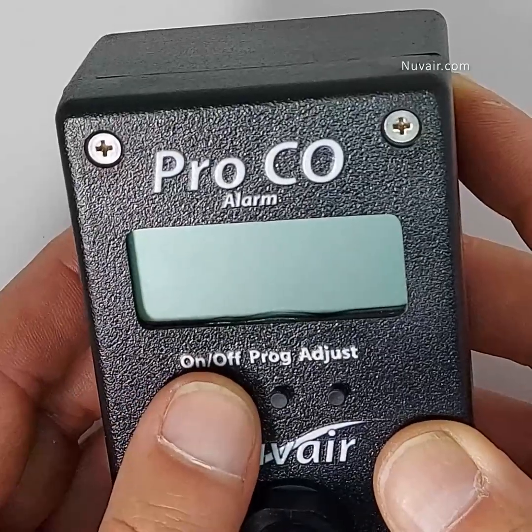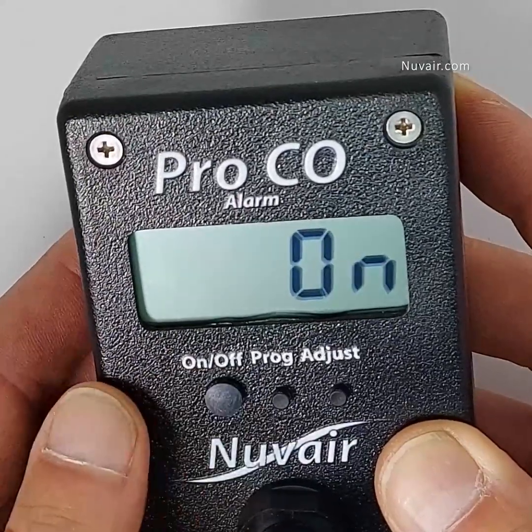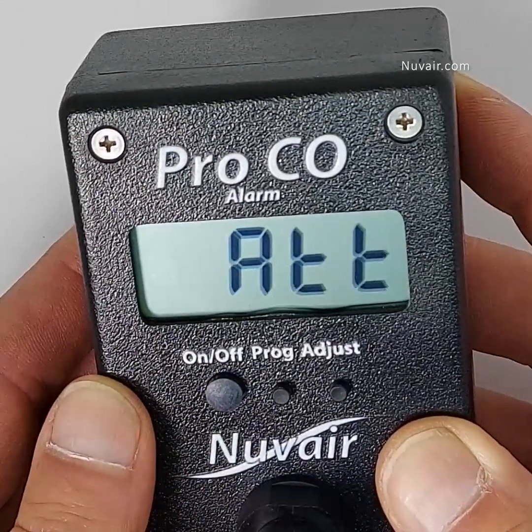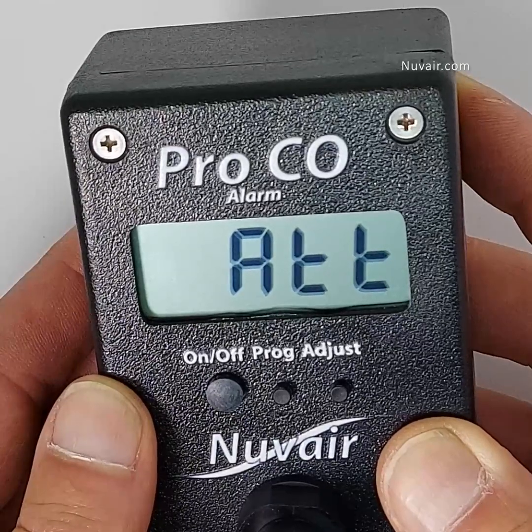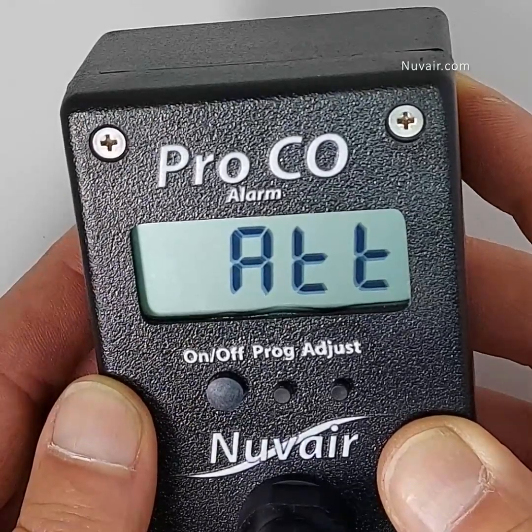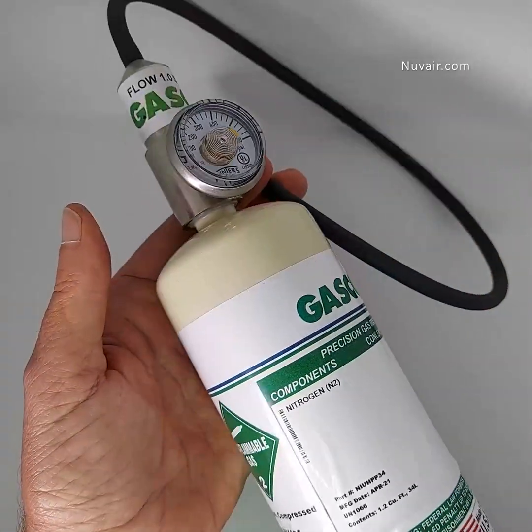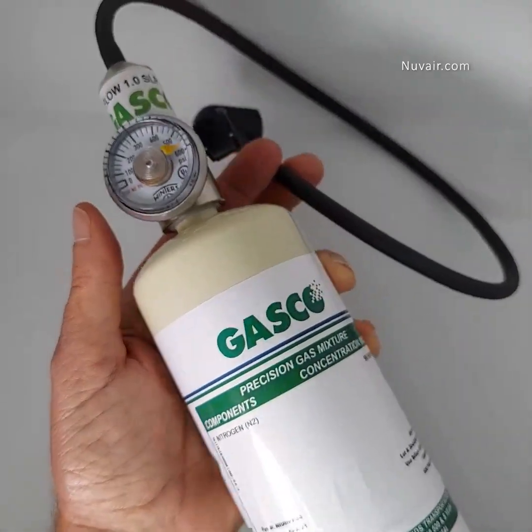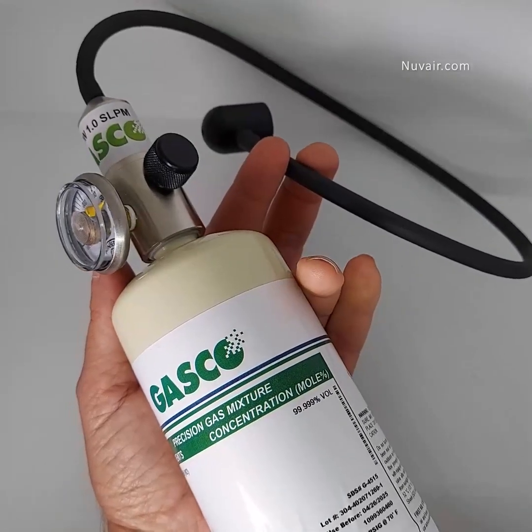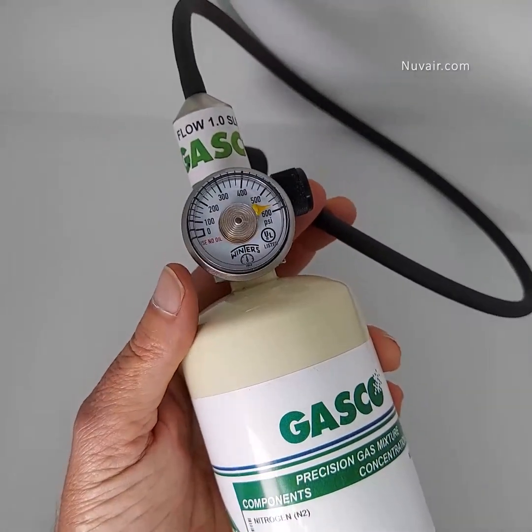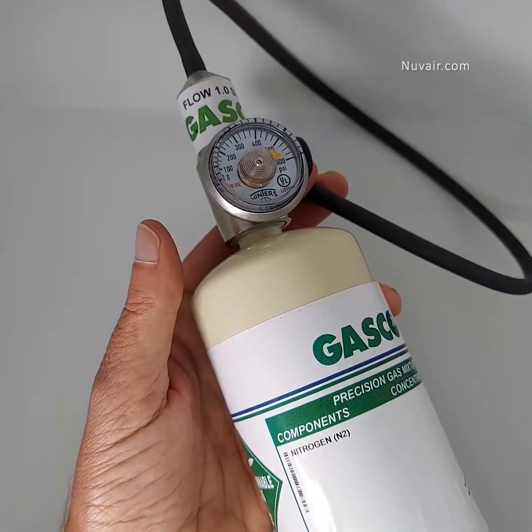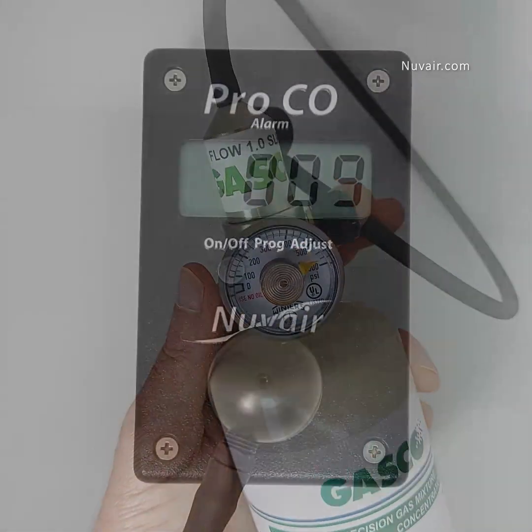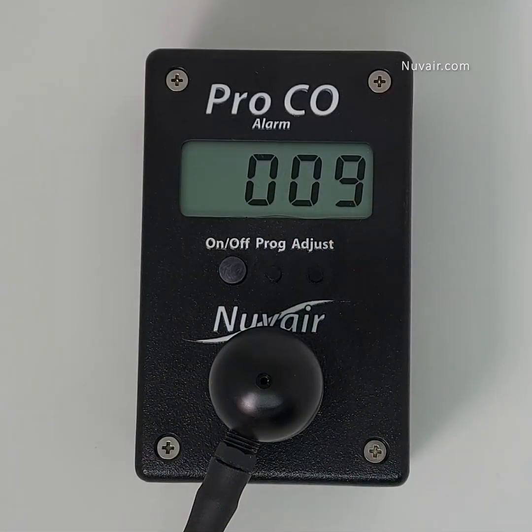To calibrate the analyzer span, follow these 4 steps. Step 1. Turn on the analyzer and program the CAL value to the CO content of the calibration gas to be used. Step 2. Connect the sensor to calibration gas and allow it to flow for 2 to 3 minutes. Flow should be regulated to 1 liter per minute, with no pressure on the sensor.